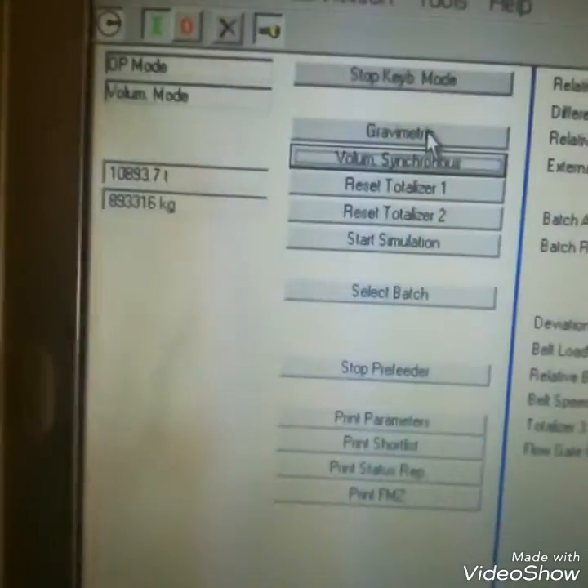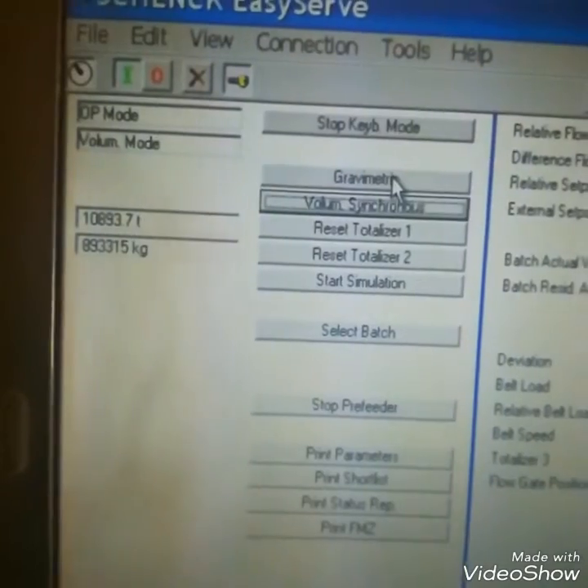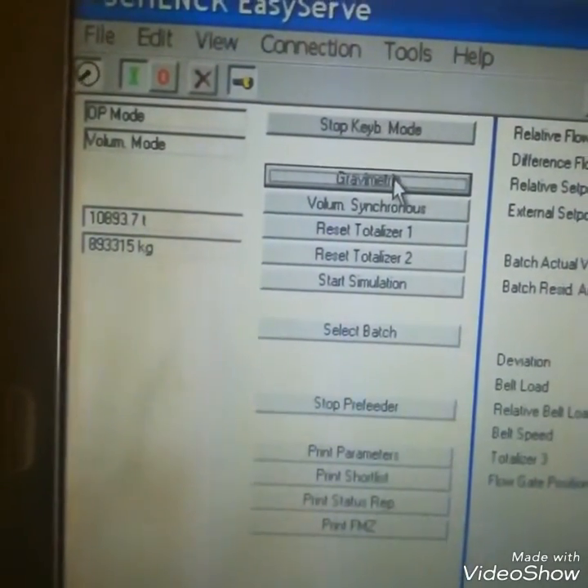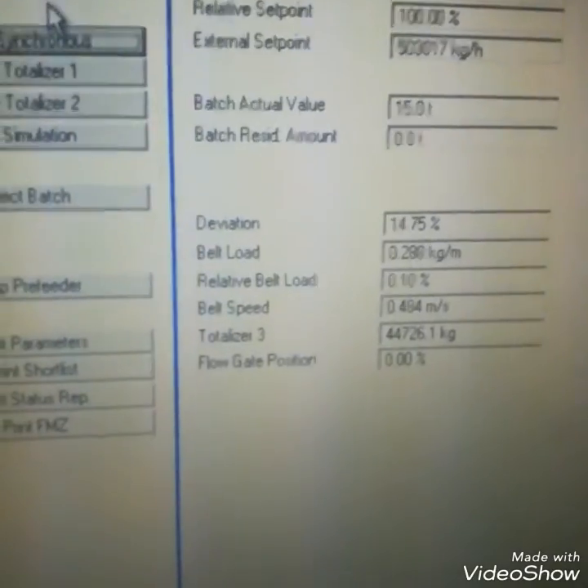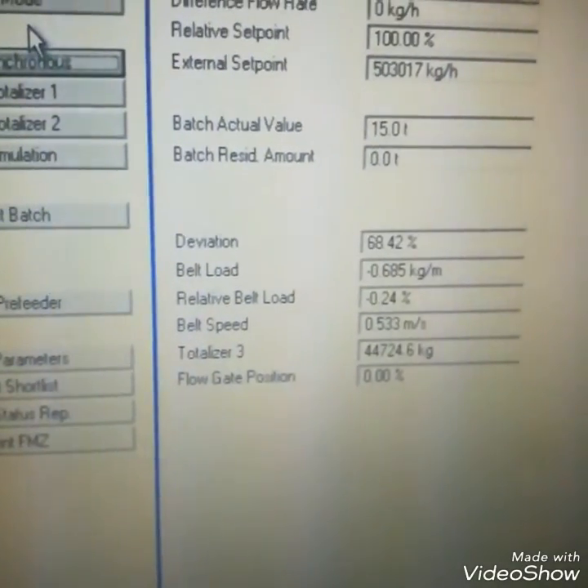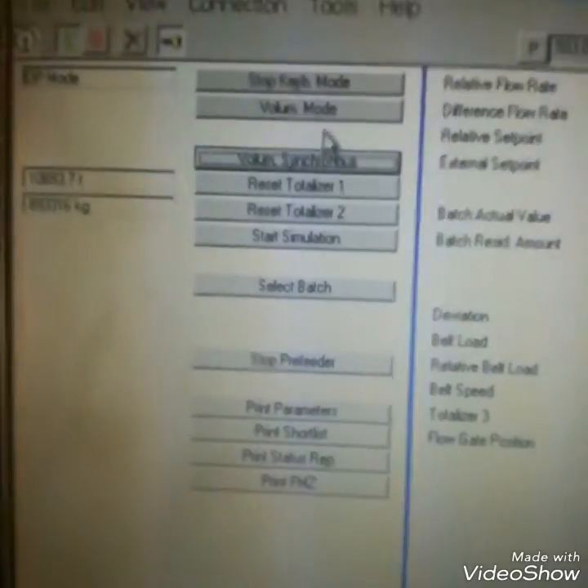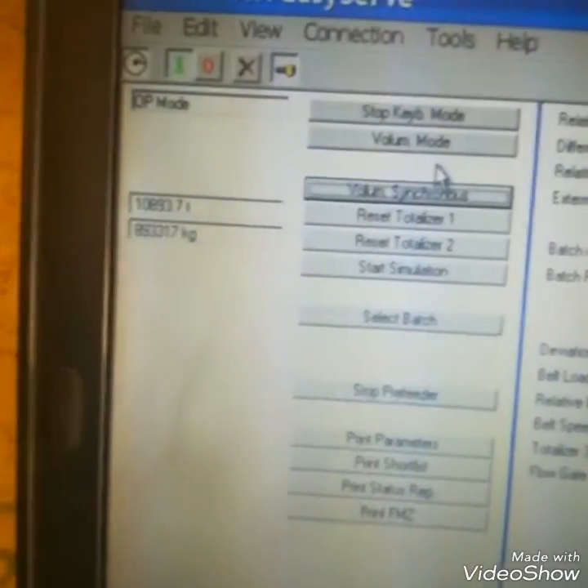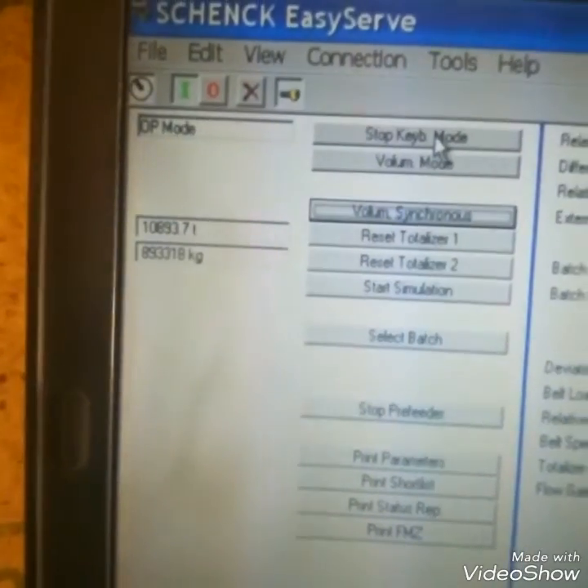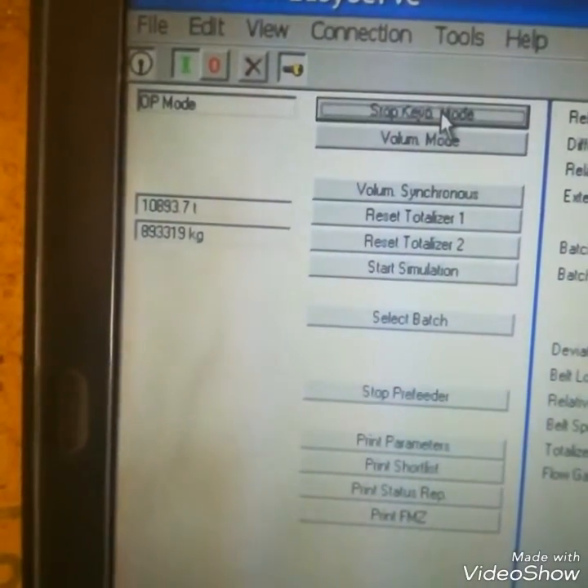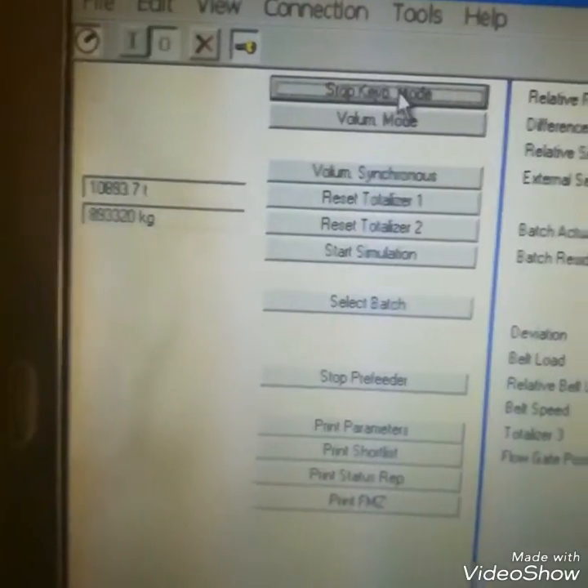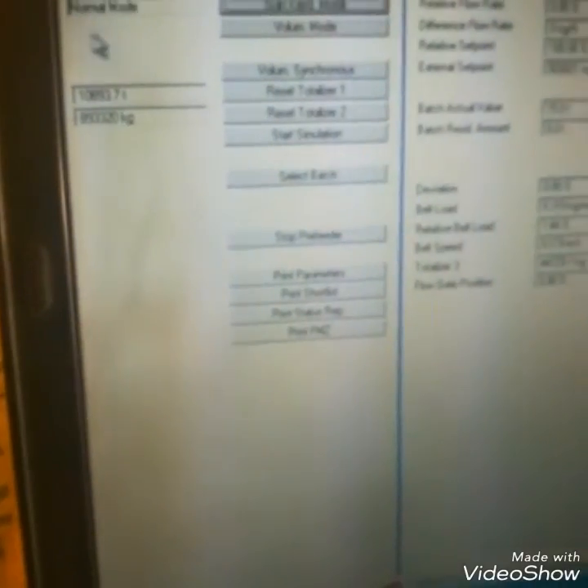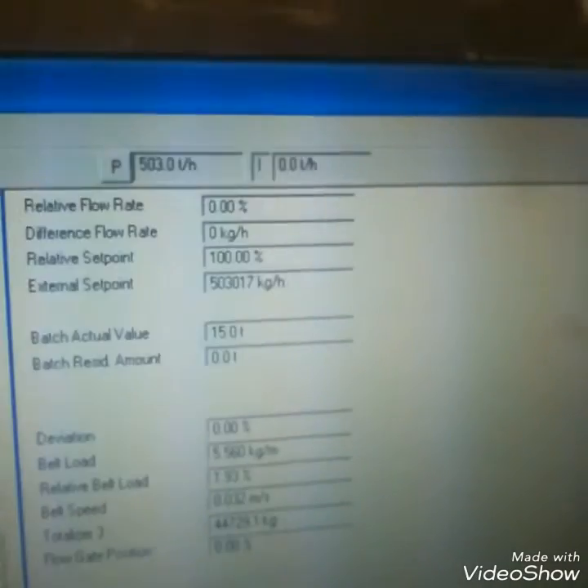Friends, I just showed you for calibration this mode. For zero calibration I will change this mode. In normal it is running in the gravimetric mode, but for calibration I will put it in the volumetric mode. After calibration I will change the mode to gravimetric and OP mode into the normal mode. In the normal mode it will run from the CCR, take set point from the CCR.